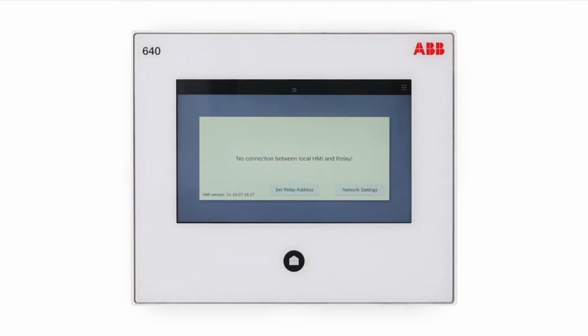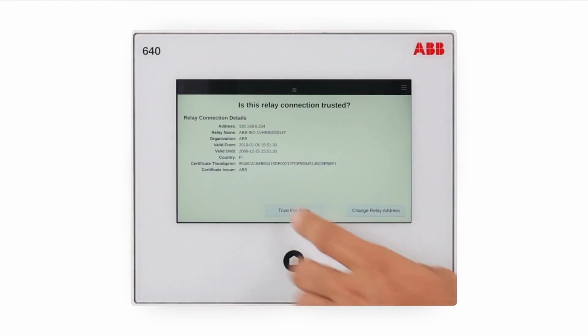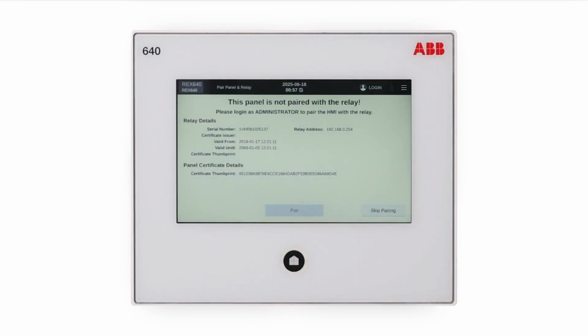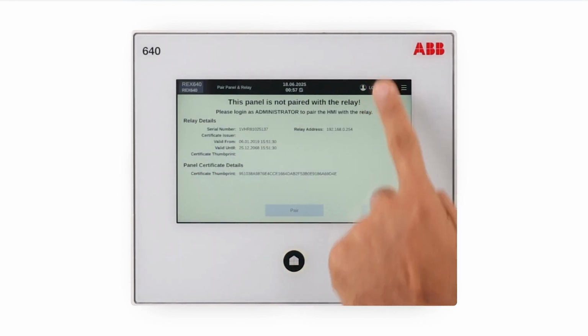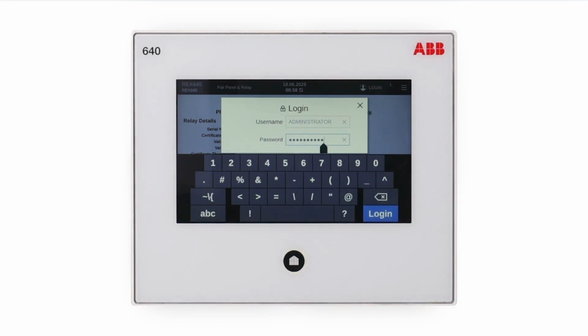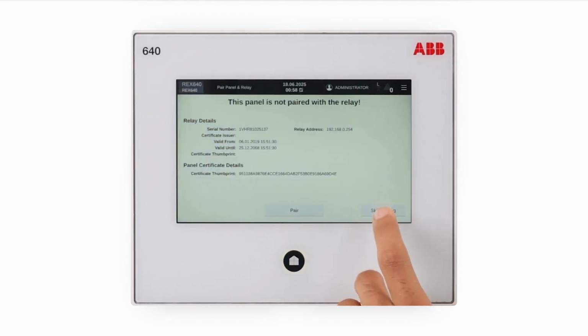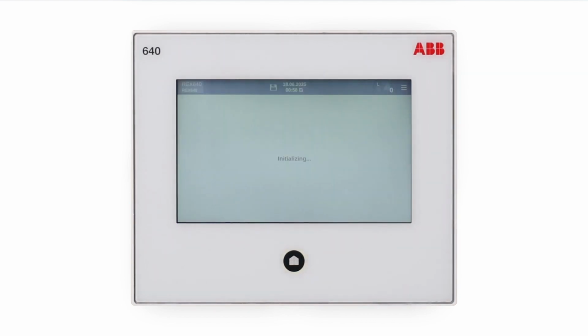Pairing local HMI with relay. To enable proper connection and functionality between the LHMI and a relay, they need to be paired. Set up communication to establish a connection between the HMI and the relay. In the confirmation window, tap Trust this relay. A page for initiating the pairing opens. To initiate pairing, log in as administrator. The default ID is ADMINISTRATOR, all letters in uppercase. The default password is remote0004, all letters in small case. Finalize the pairing process depending on the HMI used. To pair the LHMI with one relay only, tap Pair. After successful pairing, the LHMI homepage opens.